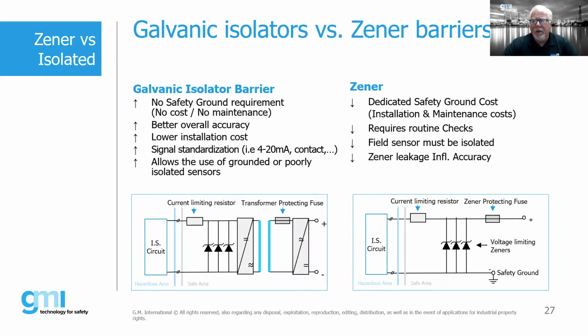Right. So a little bit of pros and cons, if you will, and we've kind of talked about this, but with your galvanically isolated barrier, again, there's no safety ground requirement and better overall accuracy. That lower installation cost has to do specifically with the fact that you don't need a ground, right? And of course, it does allow the use of grounded or poorly isolated sensors. With the Zener, you do have that dedicated safety ground and routine checks. The field sensor must be isolated. There is potentially some Zener leakage, if you will, affecting the accuracy. That is a potential issue, but generally speaking, the main pros and cons are spelled out there.